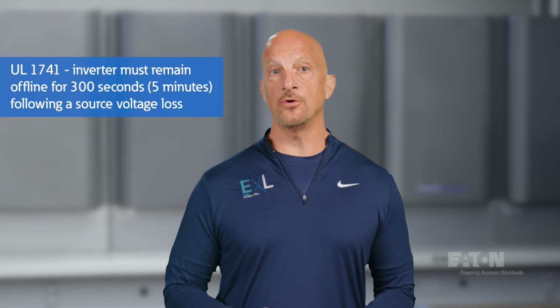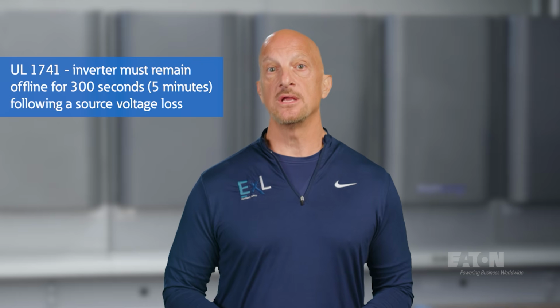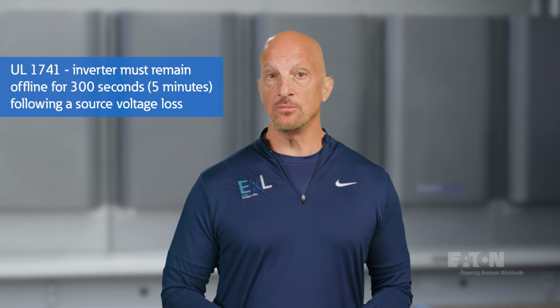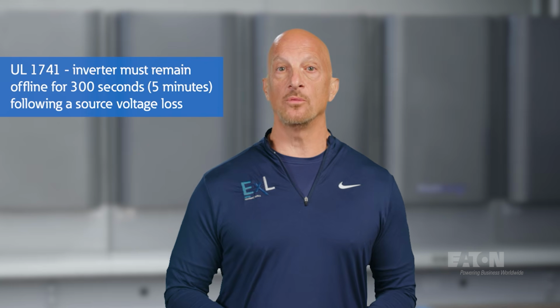If it's not set for islanded operation, the fuel cell inverter will remain off until the utility comes back and stabilizes. In this mode, per UL 1741 standards, the inverter must detect stable utility voltage for 5 minutes before reconnecting to the grid.